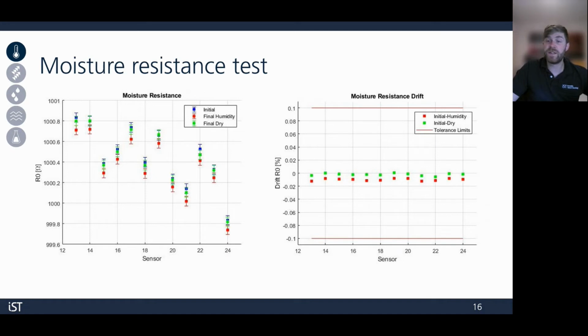Next, we have a moisture resistance test. Here we measure the resistance before and after the elements are repeatedly exposed to high humidity. And then they're dried for a final measurement. Again, here we see very minimal drift.